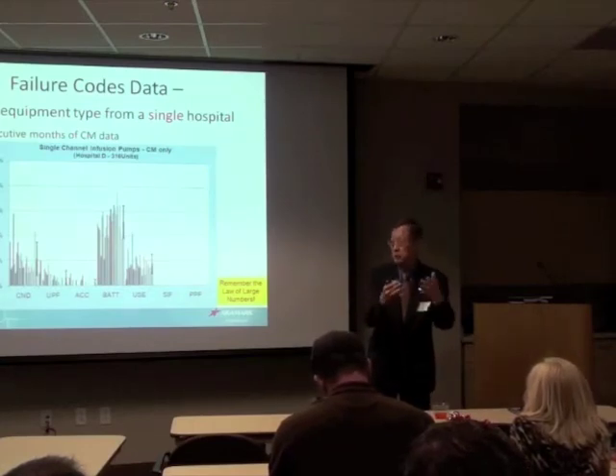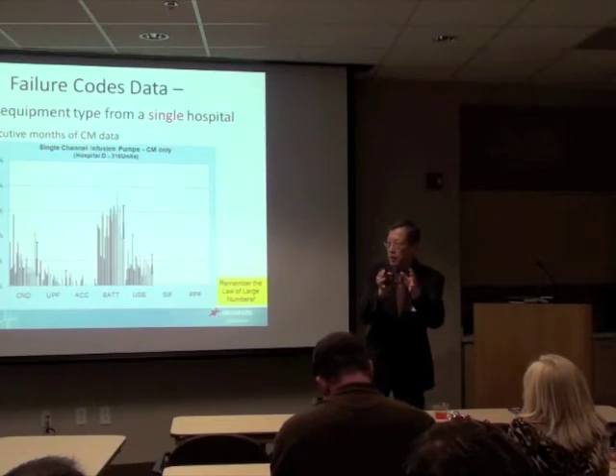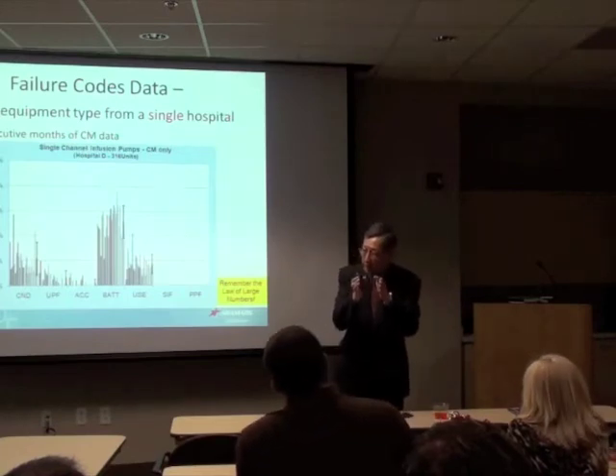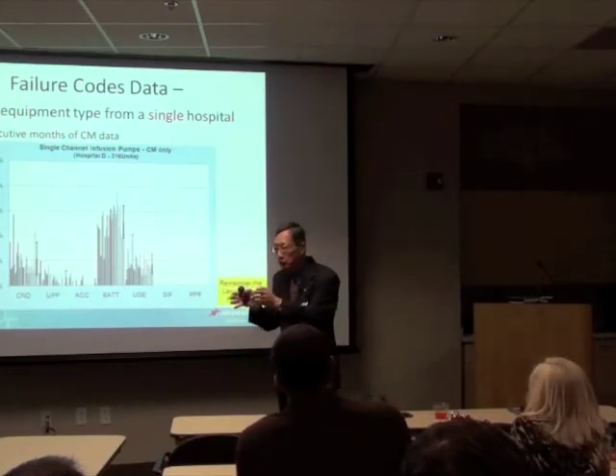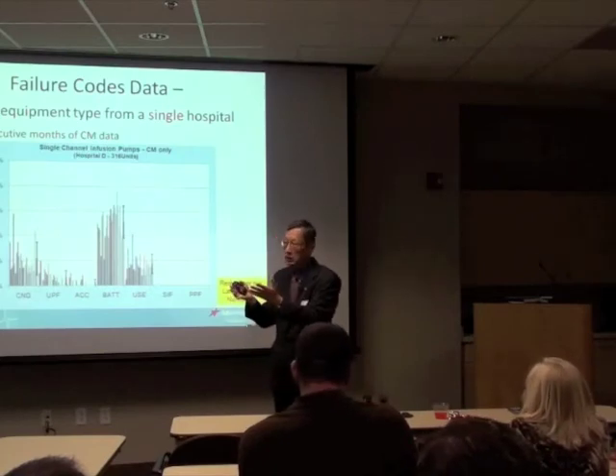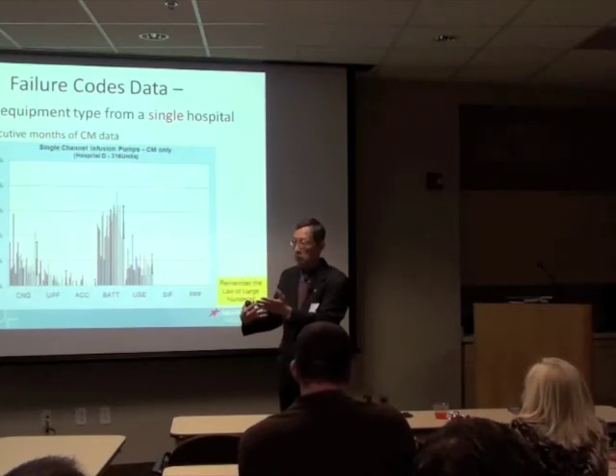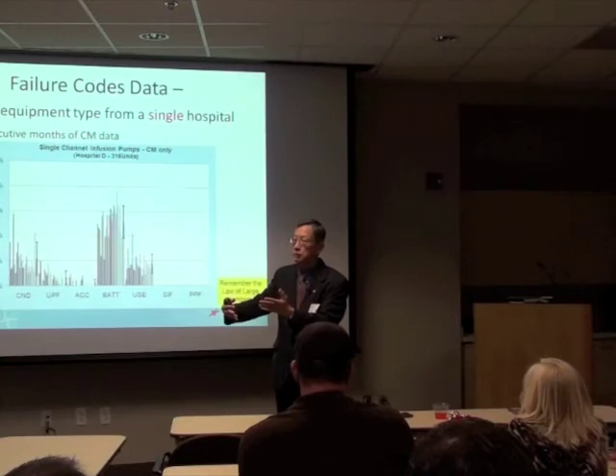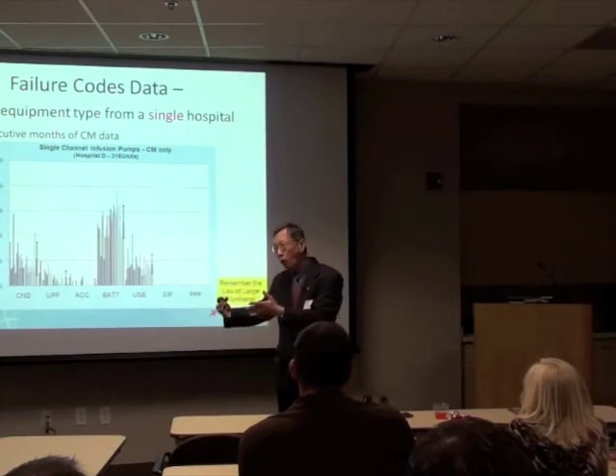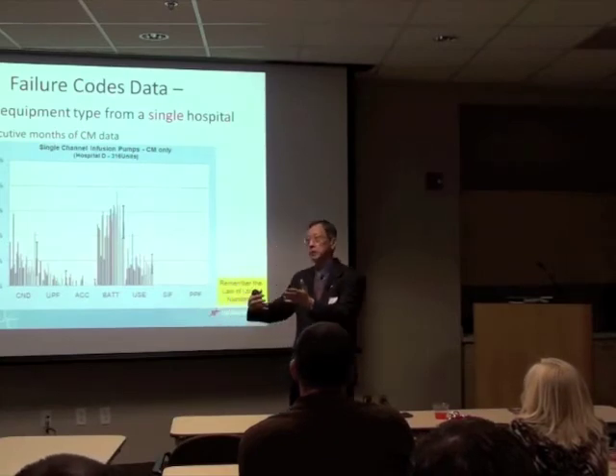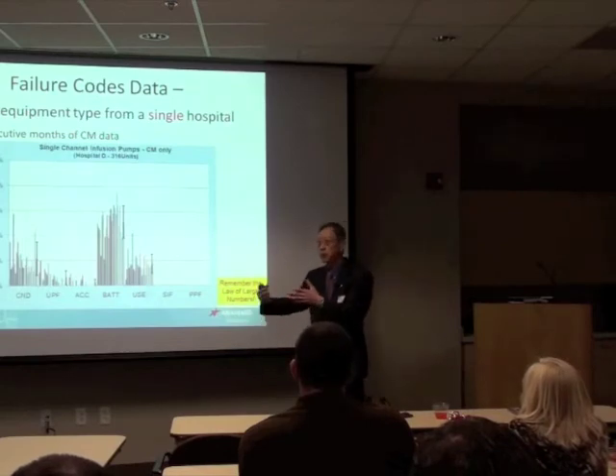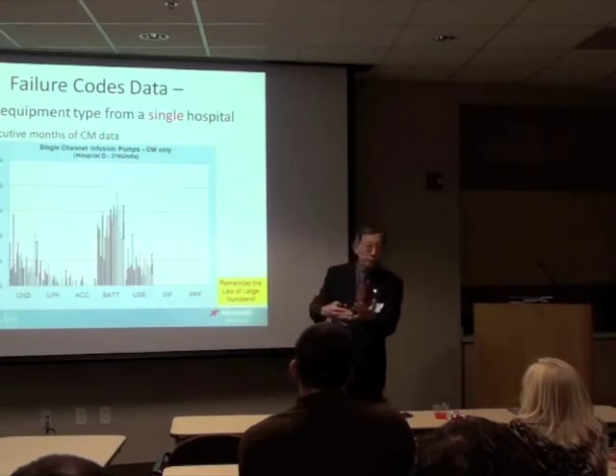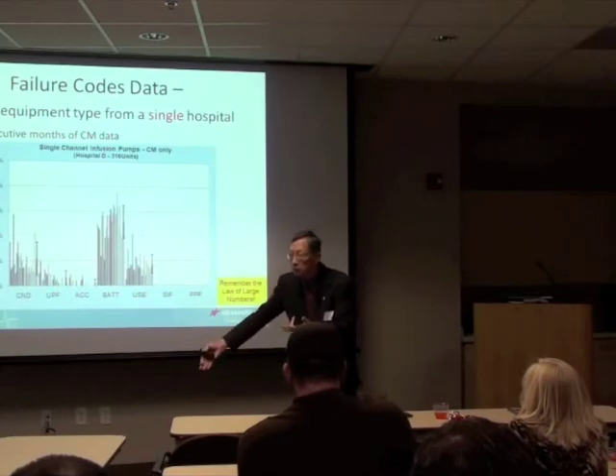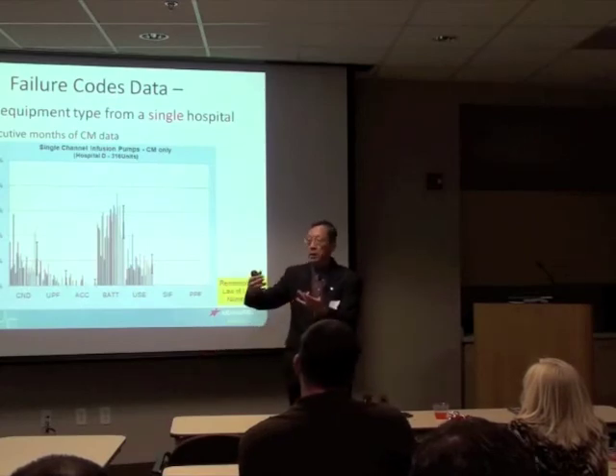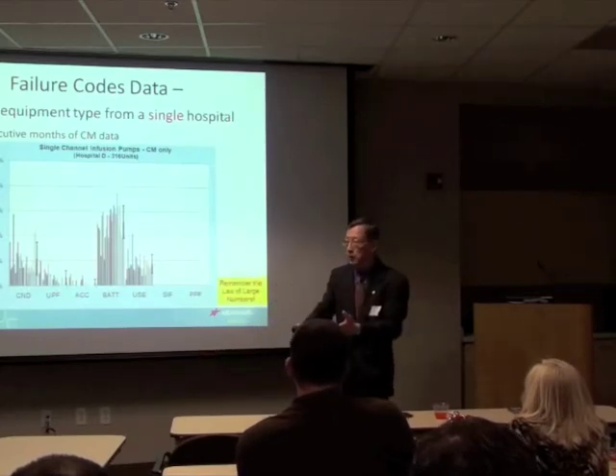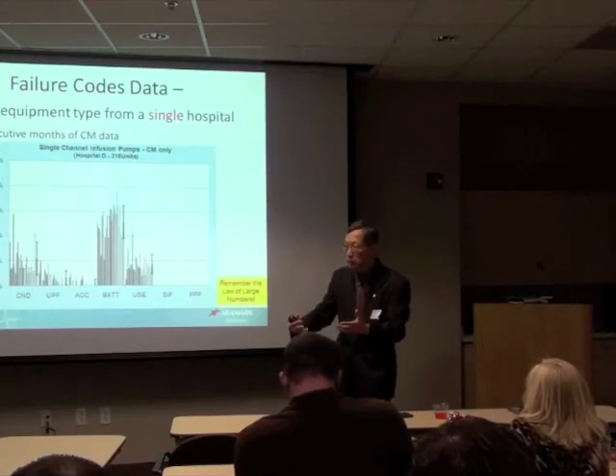So if the work order was called in because of a battery that was dead because somebody forgot to plug it in, it's easier to make sure that is the case, because then we can go back to the users and say, look, you guys need to be refreshed in training, the batteries need to be plugged in, otherwise it's not good. Or maybe another possibility is to have a team of people who help clean the infusion pump after each use and plug them into the outlet to be charged until somebody needs the pump again. So that's another way of addressing the problem.